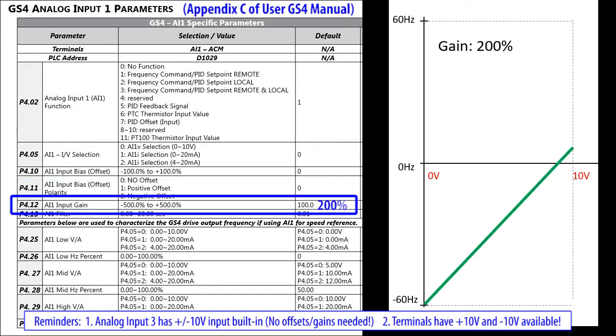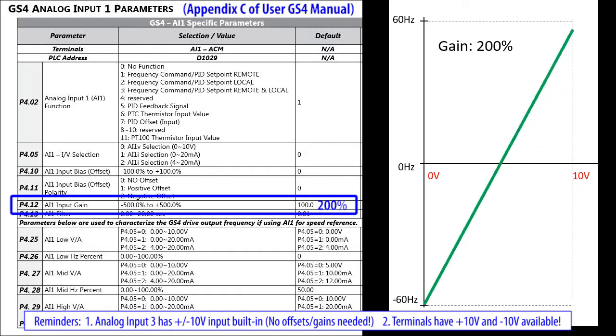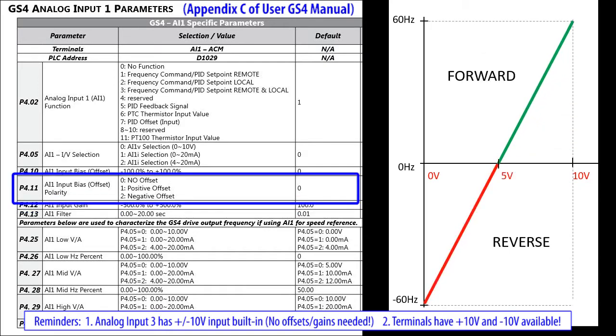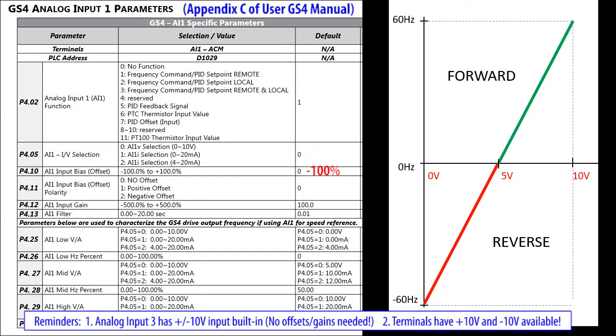Since we did that, we need to double the gain to get the full range back, which is parameter 412. We need to enable the offset in parameter 411 for analog input 1. We used a negative number for the offset value so we'll use the positive enable. We could also have used a positive offset and then told it to invert it here by using a negative enable.